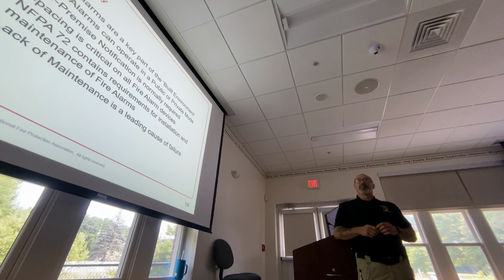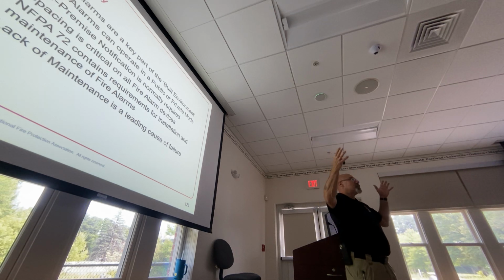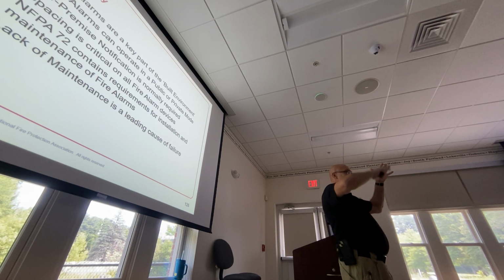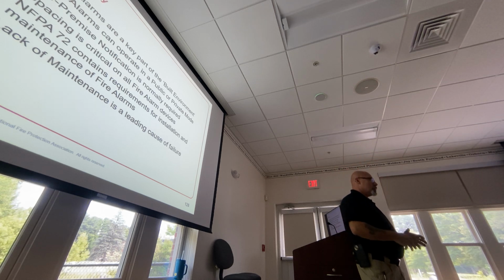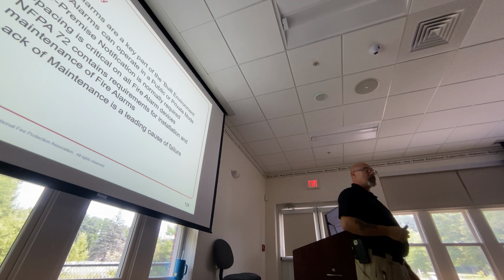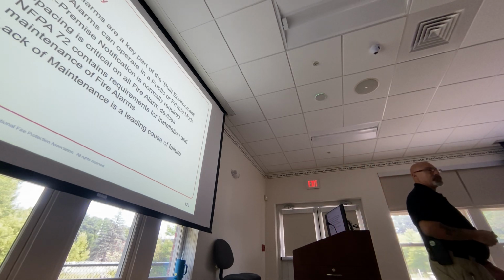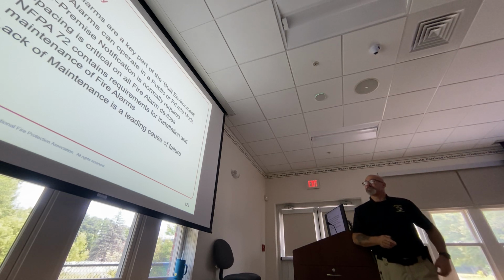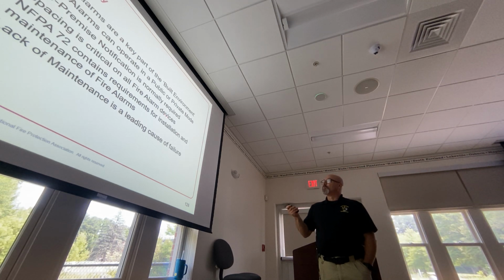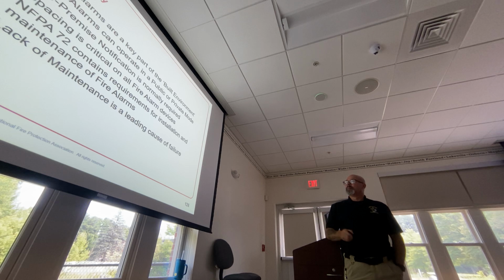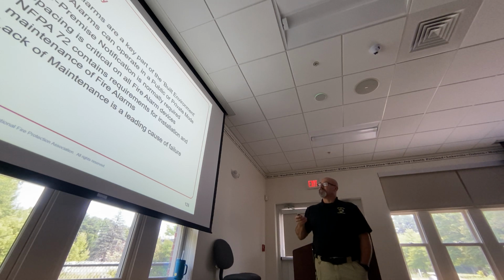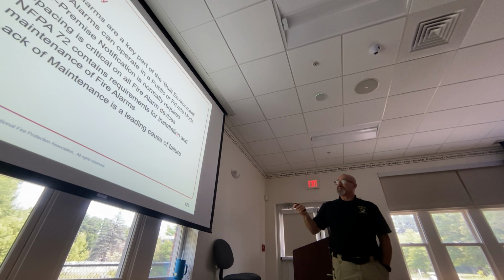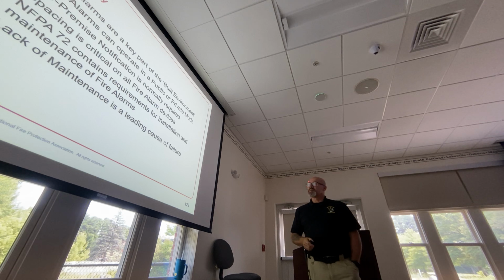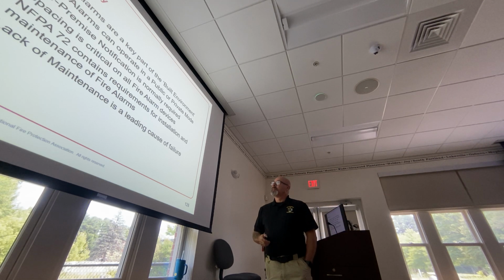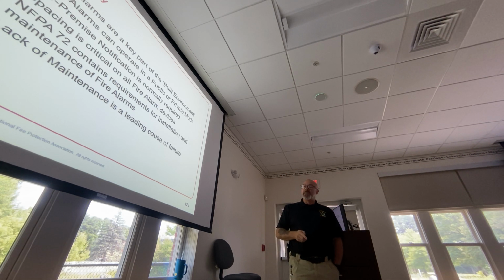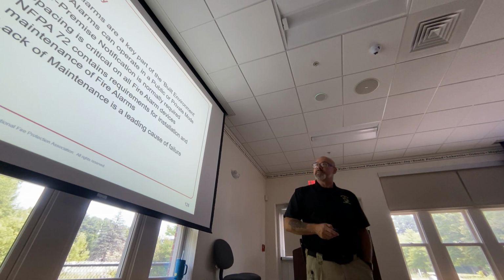Spacing is critical on fire alarm devices, just like sprinklers. You don't want them too close together because it'll cause something not to work, and there are a number of different reasons with a fire alarm system. It's super important to maintain it. NFPA 72 has the requirements for the installation and inspection, testing, and maintenance, all in one book. And lack of maintenance is the leading cause of failure for fire alarm systems.